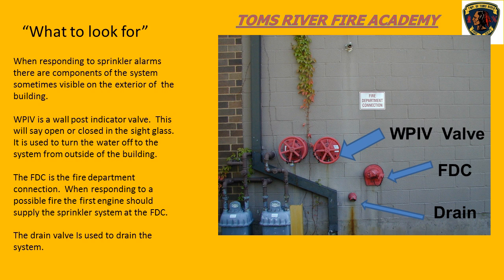Other things to look for when you're hooking up to the fire department connection. Obviously, fire department connection right here. These are wall post indicator valves. They're there for you to shut the sprinkler system down from the exterior. You do not have to enter the building. However, in order to drain the system down through the drain valve, someone will have to go in and open up the drain valve.